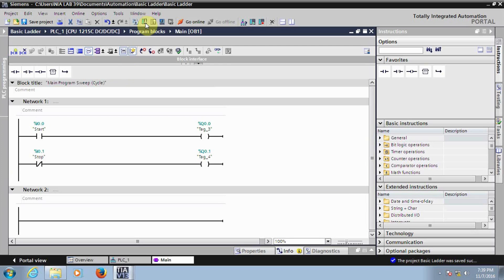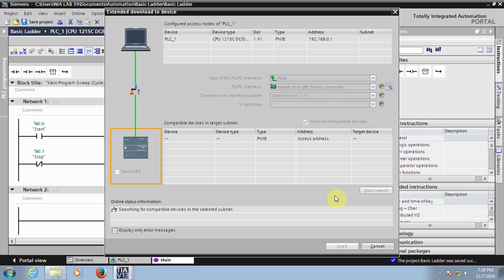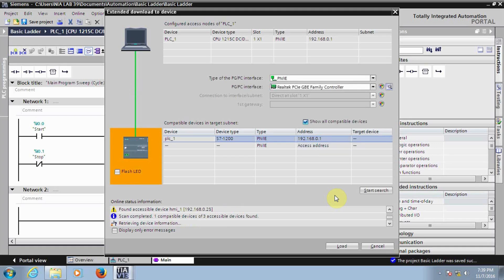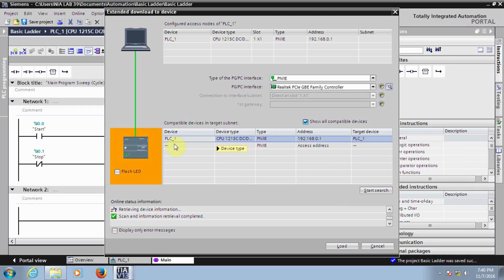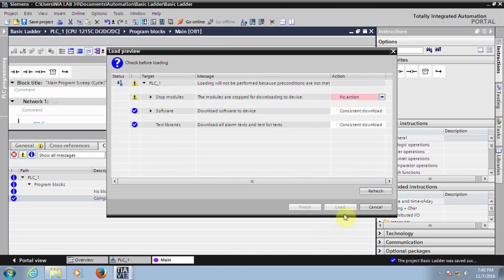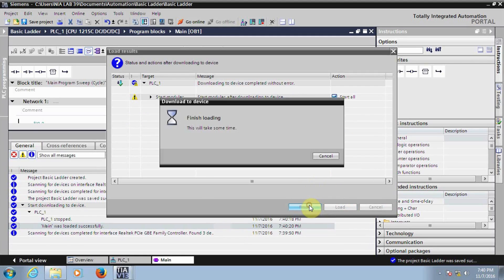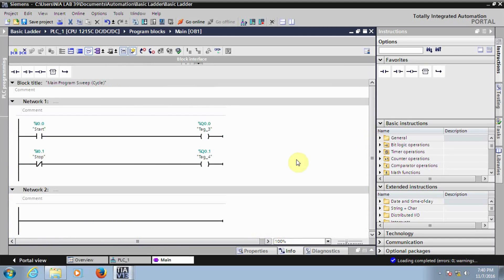Now you need to click on Download. Check the connection — that is PROFINET and the Ethernet drivers — and click Start Search. In a network you may have more than one PLC controller, so you need to select the appropriate controller and download your logic into that particular PLC. Identify your controller by its device name and IP. Once you confirm the controller, click Load. The project is now being loaded — first stop all so that the PLC functioning will be stopped, then click Load. Then click Finish. The logic has been successfully downloaded.